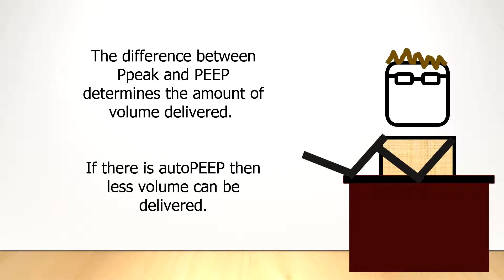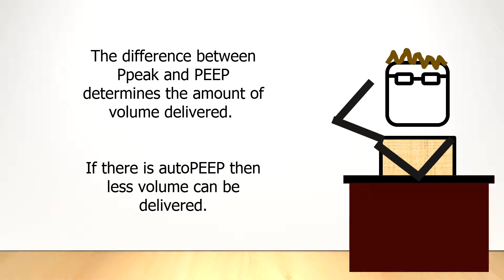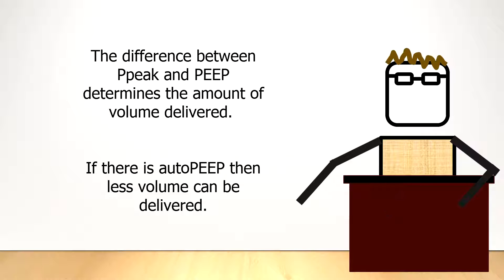You can see one of the nasty side effects of auto-PEEP in circumstances when the tidal volume that can be delivered goes down, because the pressure gradient between the set pressure and the PEEP — which is in fact higher because of auto-PEEP — causes less tidal volume to be delivered.